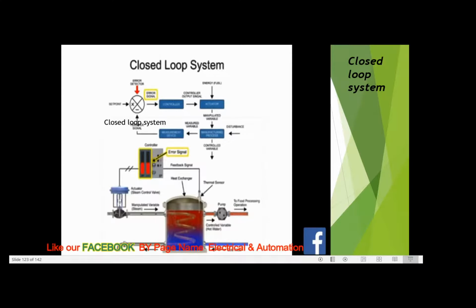The controller is the brain of the system. It receives an error signal as its input and provides an output signal to the final control element, or actuator, in this example. A signal from the controller causes the controlled variable to match the set point using the actuator of the system. The flow valve represents the actuator, where steam flow is controlled. The amount of energy or steam in this example, altered by the actuator, is the manipulated variable.